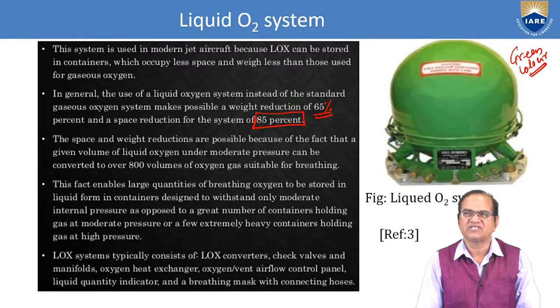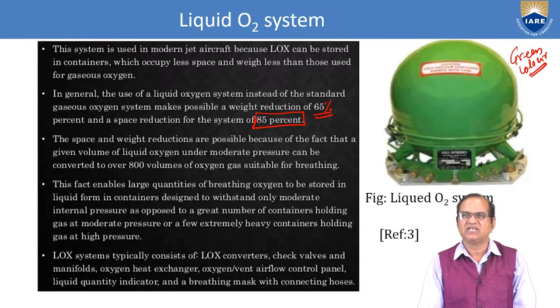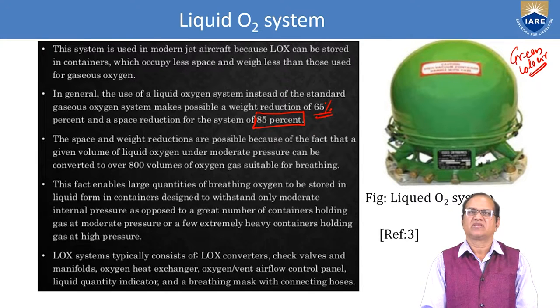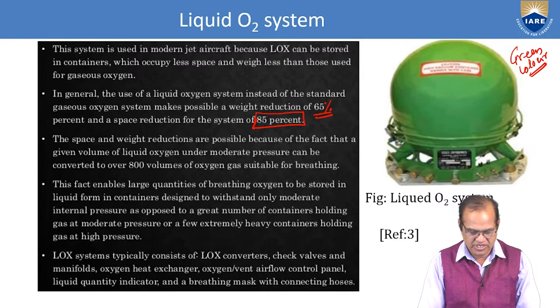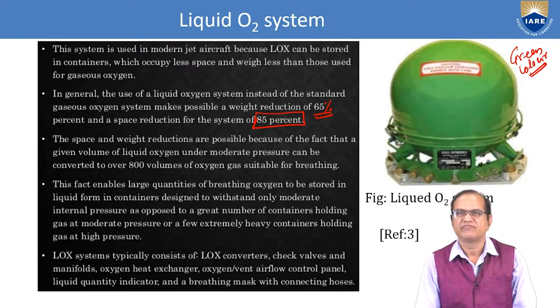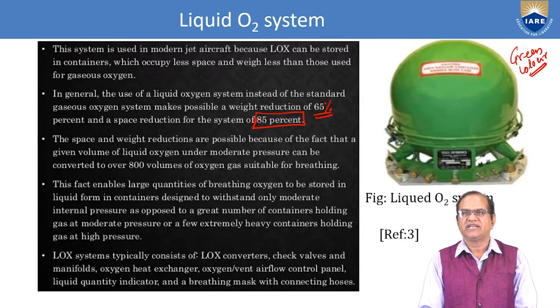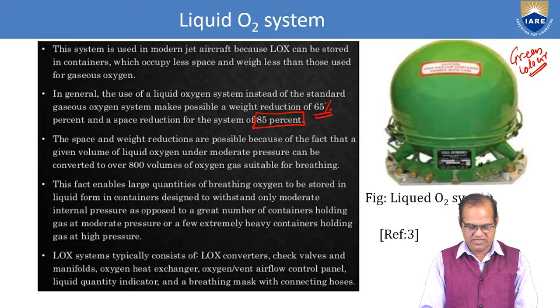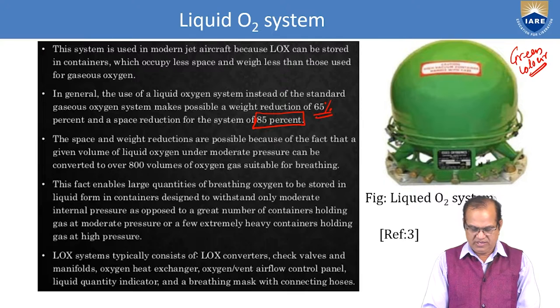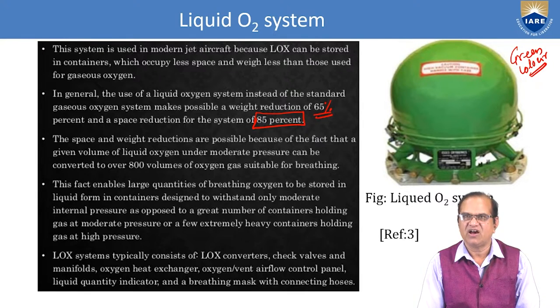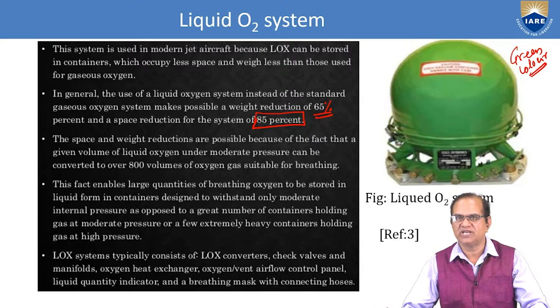The space and weight reductions are possible because a given volume of liquid oxygen under moderate pressure can be converted to over 800 volumes of oxygen gas suitable for breathing. This enables large quantities of breathing oxygen to be stored in liquid form in containers designed to withstand only moderate internal pressure, as opposed to a great number of containers holding gas at moderate pressure, or a few extremely heavy containers holding gas at high pressure.